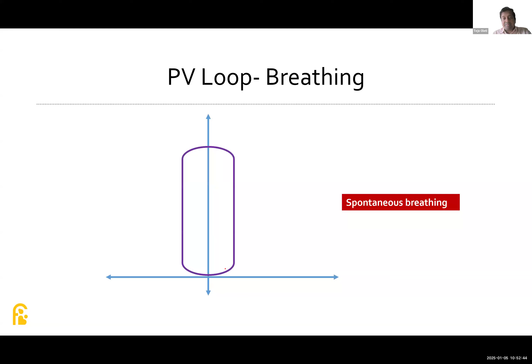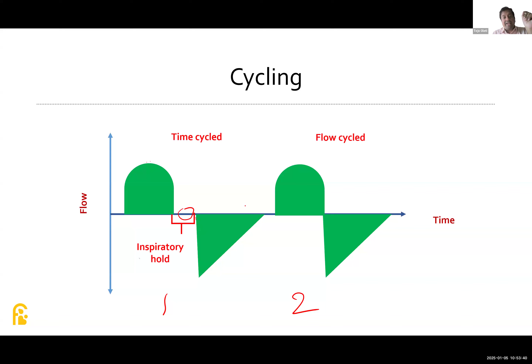Cycling, we know that there are 2 types of cycling, discussed yesterday also, time cycle and the flow cycle. Major difference you can observe in this first graphic versus the second graphic. There is no gap here. Why has it disappeared? In the time cycle, what happened here? The flow has increased. Once the desired limit or control is reached, it has come back to 0. Because the baby's inspiratory time has not been completed as we kept it, there is a gap before it can go into the next phase of the respiratory cycle. So this is the inspiratory hold that will be there in your time cycle ventilation. In a flow cycle ventilation, you will not be seeing that inspiratory hold.